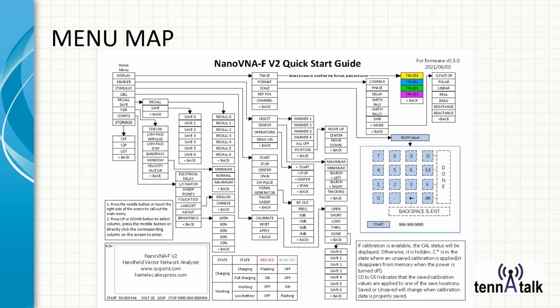So now let's take a quick look at the menu map. All right, so this is your main top menu. The first thing you'll want to do is go to the config page, and that will bring you down here. One of the first things you want to do is set the sweep points to maximum. On the -FV2, you can set 301 data points to get the maximum resolution. Default brightness is also 80%. I would set that to 100% right off the bat. I wouldn't worry about the rest unless the language came up as Chinese, in which case I'd switch it to English. So that's where you'd find that to do that first thing.